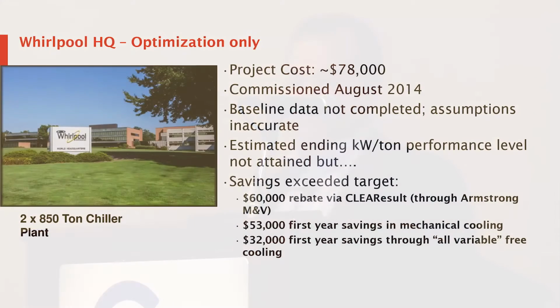And over the course of the first 12 months, which was the only time we measured it, they saved 31%. So it was almost instant. They could see the drop, and they could see it sustained. So this one I like to talk about because there were no other changes. There's nothing else in that building changed other than the way they sequenced equipment. And they had already set everything up. They had chillers that could run in parallel, they had variable flow, and they had a pretty decent cooling tower system.